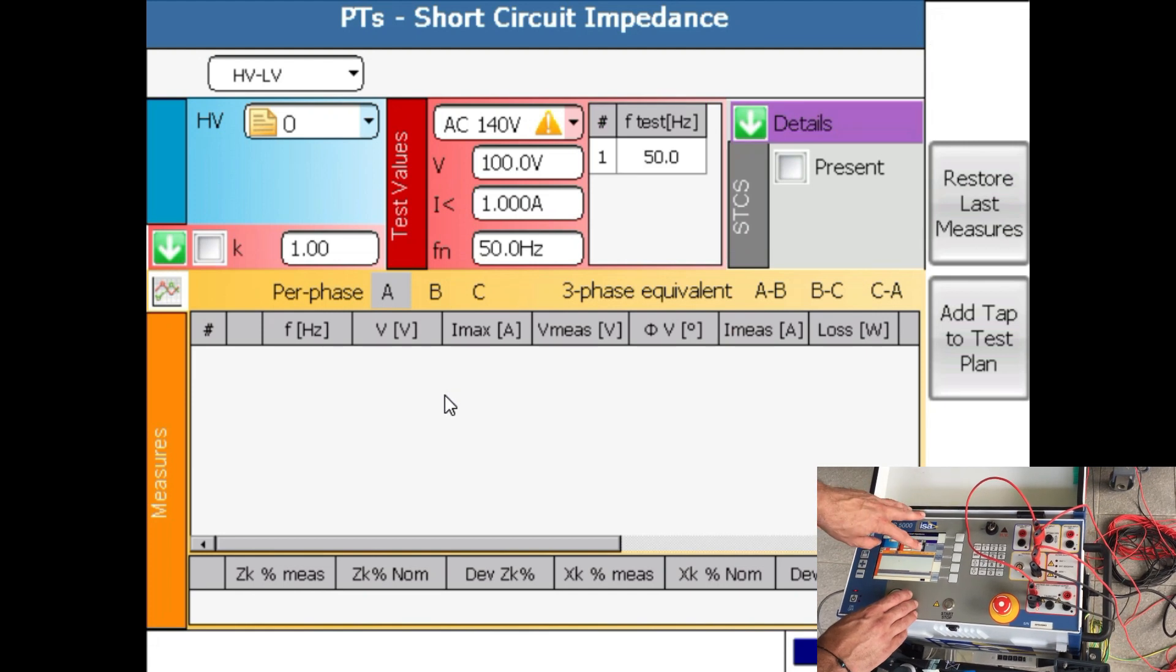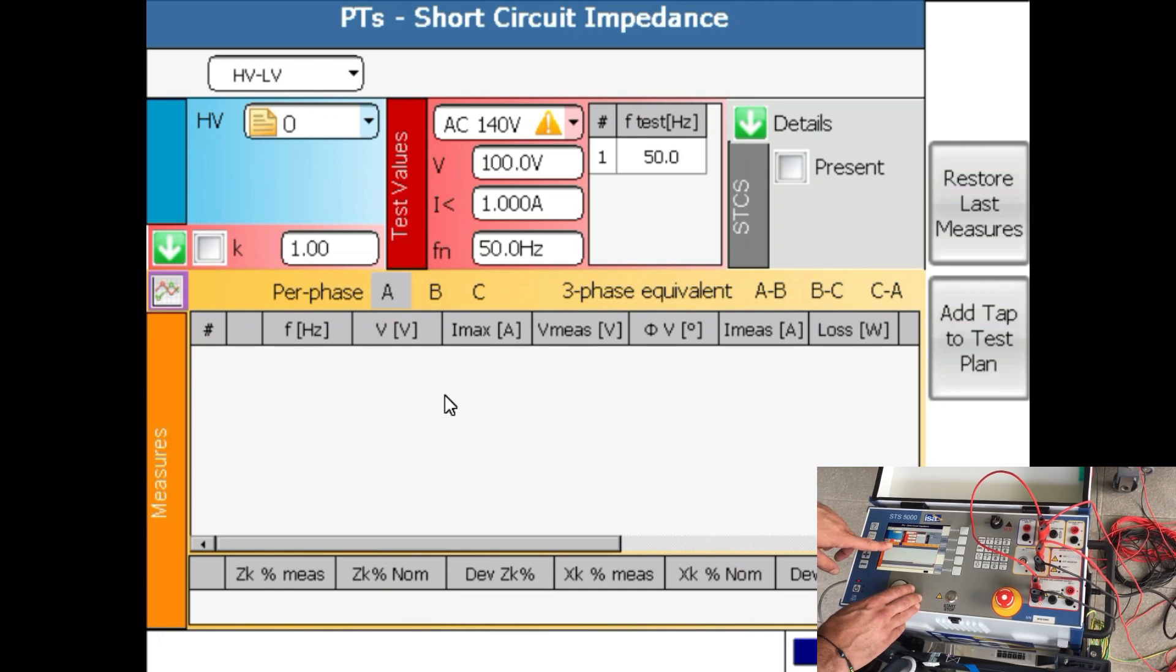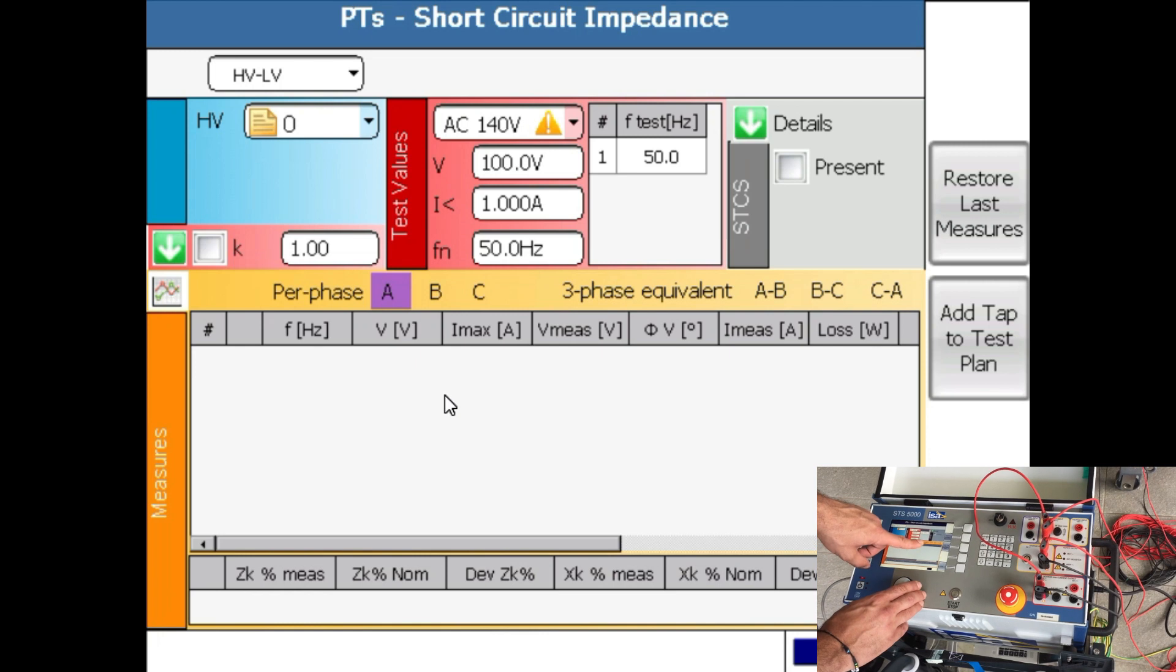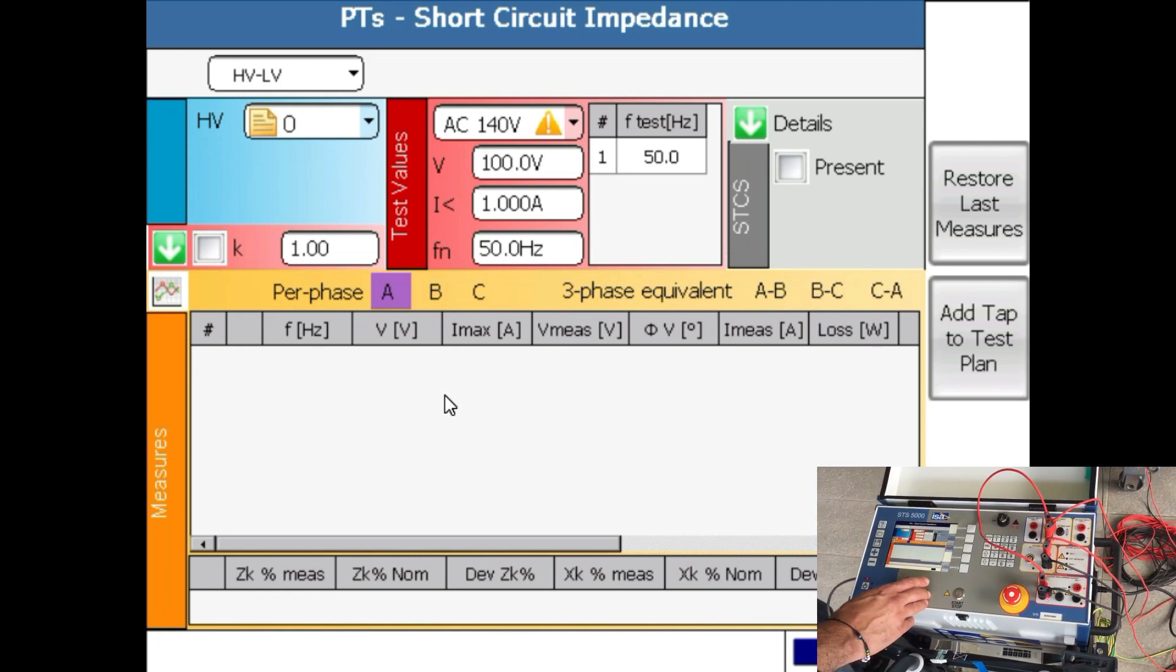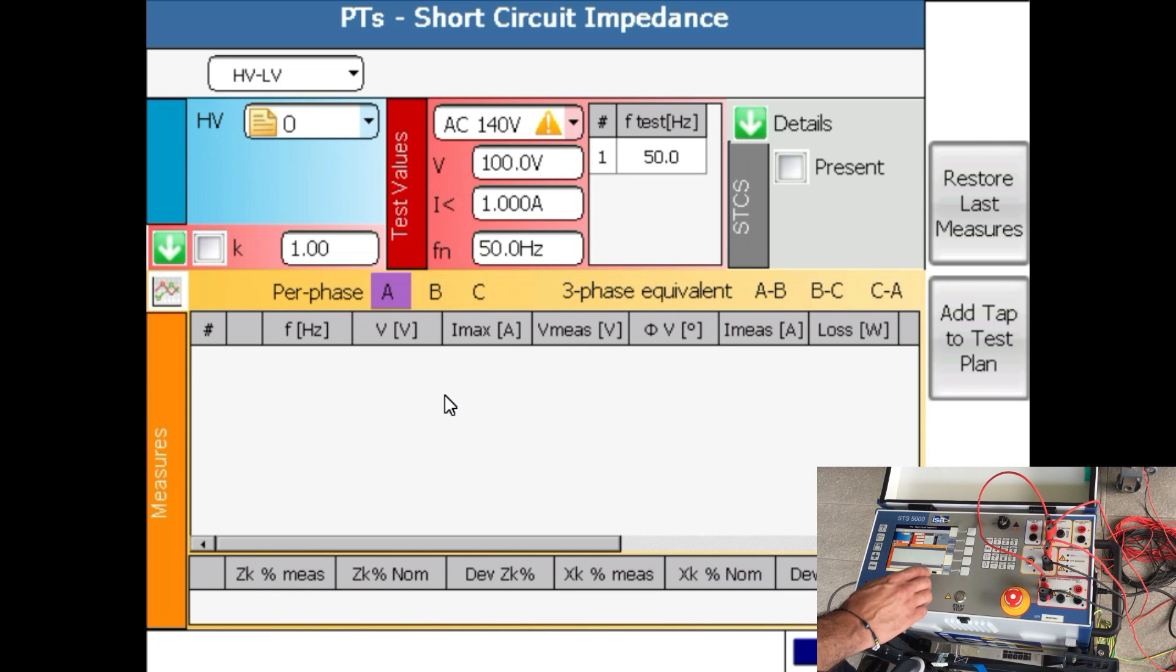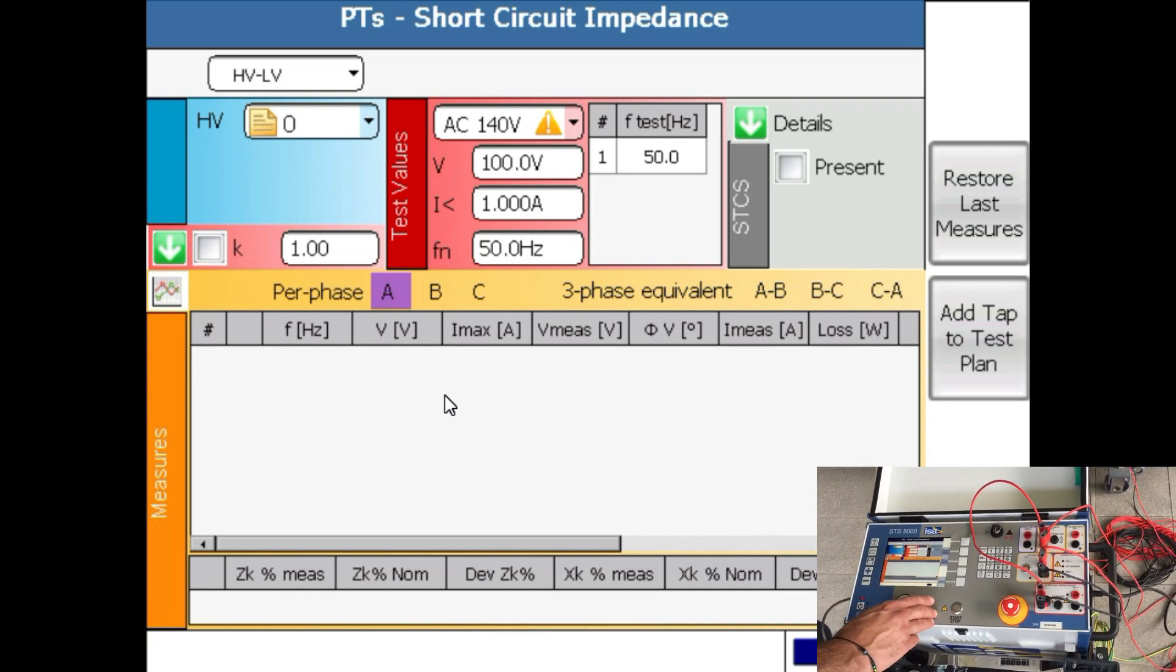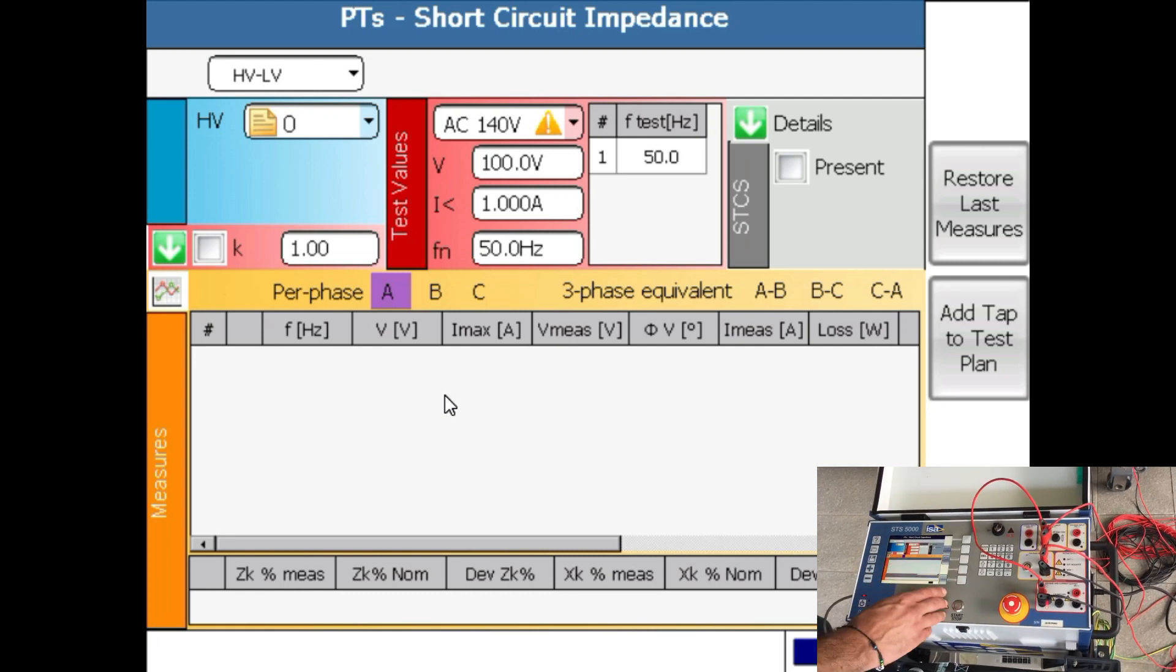Proceeding, I'm not using STCS for now, so I'm leaving that as it is. Then I need to decide whether I will do it per phase test or a three-phase equivalent. Three-phase equivalent is done in 80 or 90 percent of the cases because the number you're getting on the nameplate is done in the factory using three-phase equivalent method. Three-phase equivalent has to be used if you have a delta on any side of the transformer. Since I have a DYN 11, I have to use three-phase equivalent.